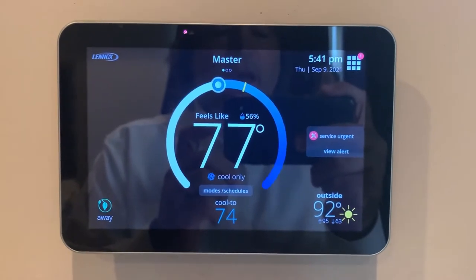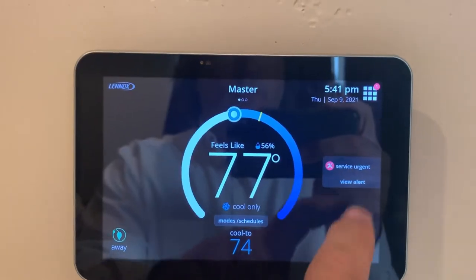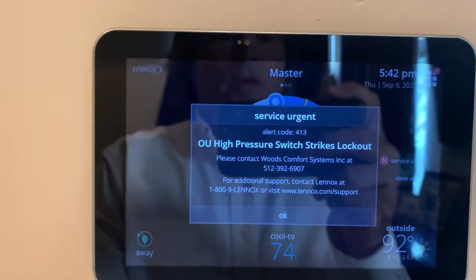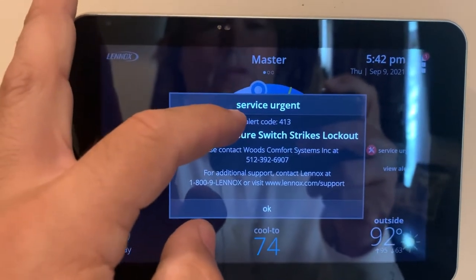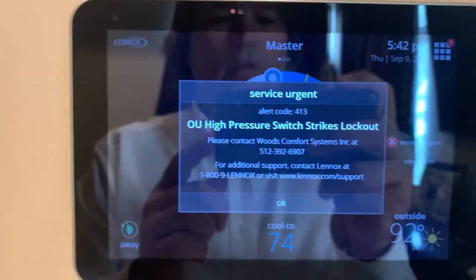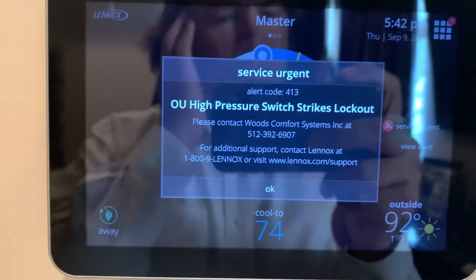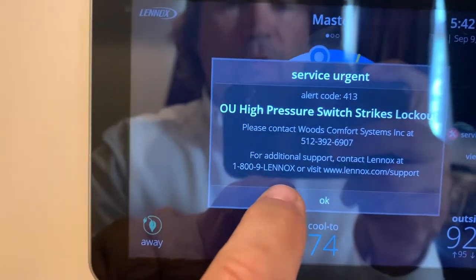We've got an issue here with a Lennox iComfort heating and cooling system. We've got a service urgent alert that you can view, and this tells us that we've got service urgent alert code 413 — outside unit high pressure switch strikes the lockout. So something's going on with that outside unit; it must have some kind of high temperature or high pressure switch indicating the compressor is having a problem.